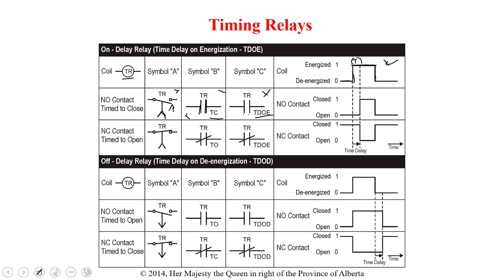If it's a normally closed contact and it's time delay on energization, you'll see that we draw the contact in the closed position, and because it's a time delay on energization, it's an up arrow. And so for normally closed, this says time to open, or TDOE with a normally closed contact. There are other ways to write it.